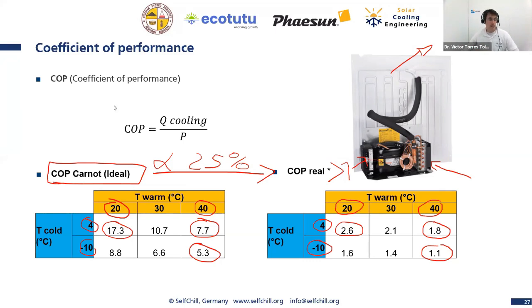That's why we don't call it efficiency, we call it coefficient of performance, because actually the efficiency of the cooling of the heat pump will be, in this case, this ideality factor, right? This 25%. The compressor has an efficiency, yeah? You have electricity and then compressed energy, yes, below 100%. The fan has an efficiency always below 100%, but because we are pumping energy, we are not creating energy, right? This is not a creation of cooling energy. This is pumping energy. That's why we can deal with coefficient of performance higher than 100%. This is very important that is clear for you.